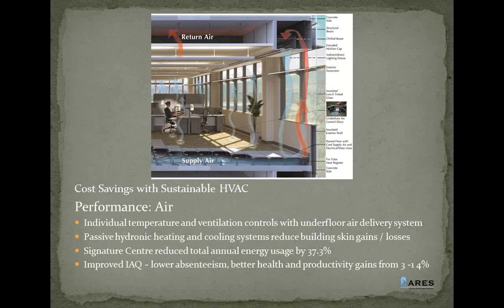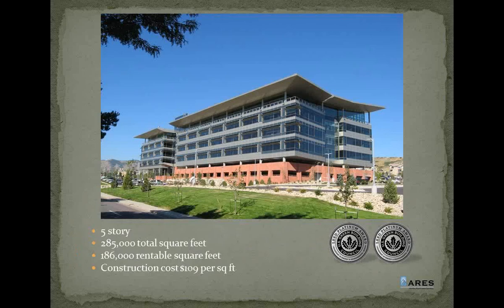In our case, having two systems created an annual reduction in energy costs of almost 38%. It increased the indoor air quality because it's a single pass system instead of your standard turbulent system. The air comes out of the floor, passes through the space. We stratify the air so you're cool up until about 6'6", and then it warms naturally. That air then returns back into the RTUs and is sent back through the space. The other thing that the HVAC system did is allow us to lower our floor plates to 13 feet floor to floor.